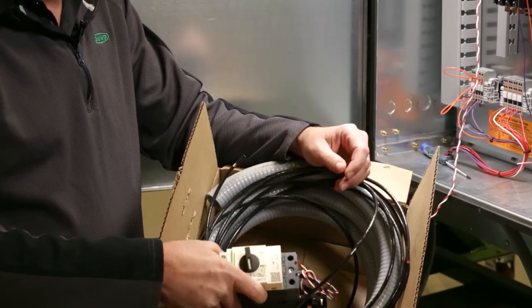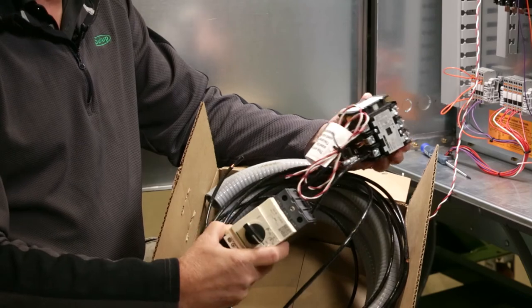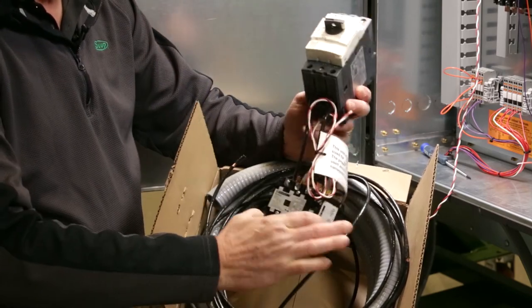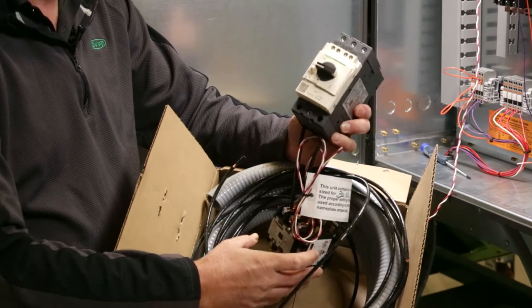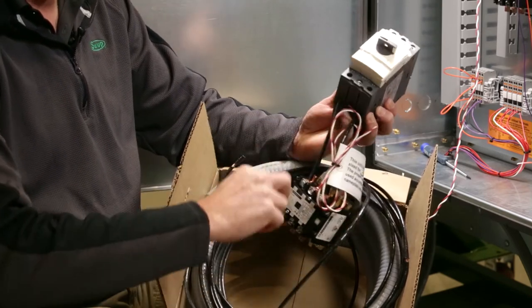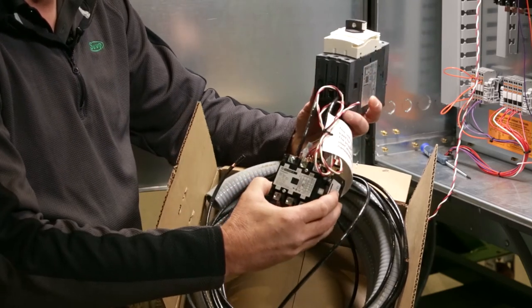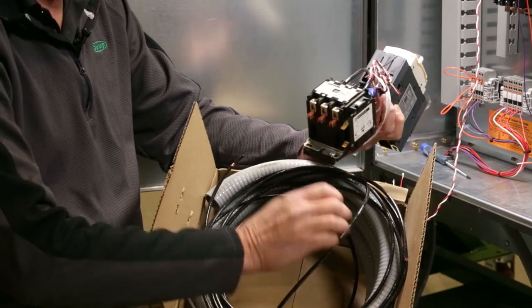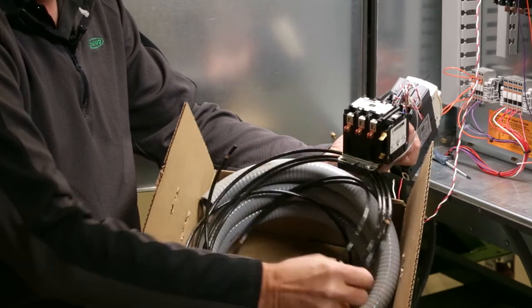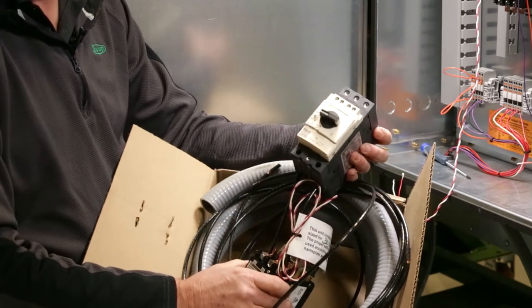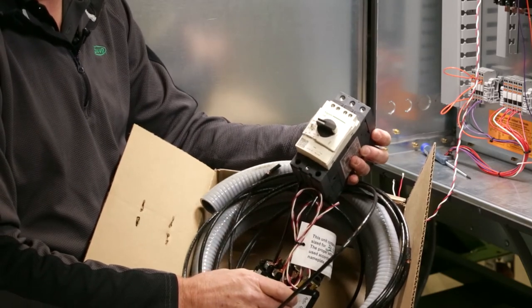If you purchase a contactor kit from Sukup Manufacturing, you will need to specify the horsepower ratings for what is required. It will come to you with the starter protector and an auxiliary contact installed, wiring down to the magnetic starter and the coil wiring. Also included in the kit will be conduit and wire to take power from our main power box distribution panel into this auxiliary box.